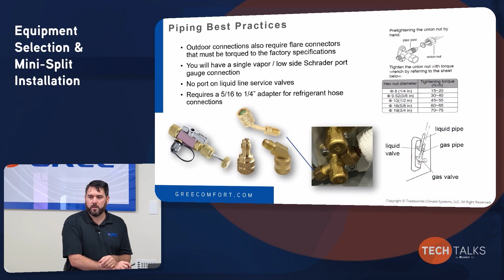So the only way you could have another port, they would have to run a separate line outside that cabinet and give you essentially a permanent suction port. Right. And then you'd also have to have a permanent discharge port. So it's going to be more expense, more piping. And when we get into troubleshooting, I know we're going to talk about it. We'll actually demonstrate using them. We have the service tools. There are a lot of other ways you can get to the same answers that you're looking for without necessarily having to have those ports.